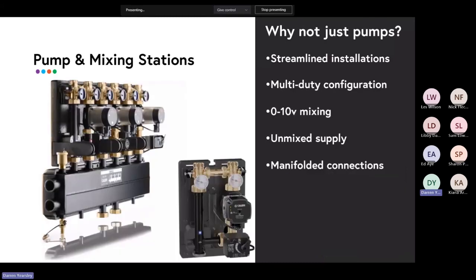More and more, we're starting to use pump stations. So a pump station is just a very easy and convenient and tidy way. It's an insulated clam. It gives you multifunctions in one group. So you've got a pump with isolators, check valve, flow and return, temperature gauges, and there's a range of headers where you can join multiple pump stations together. And I'll show some applications where we do that.